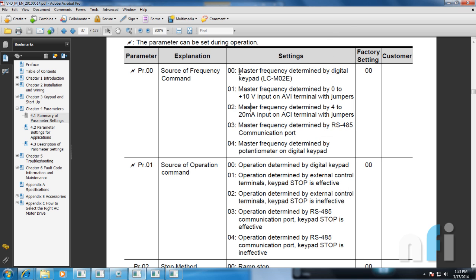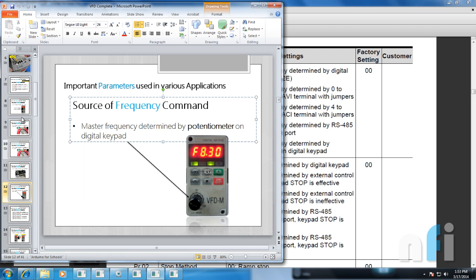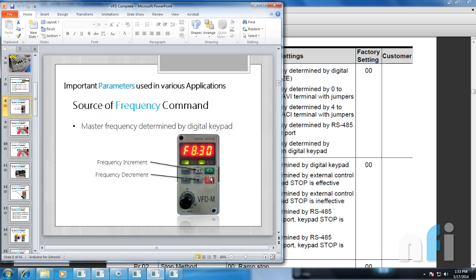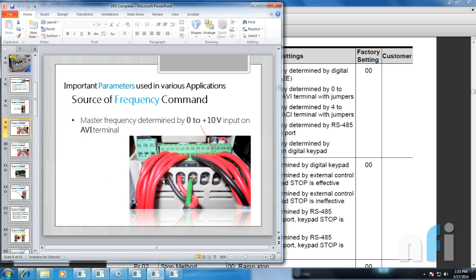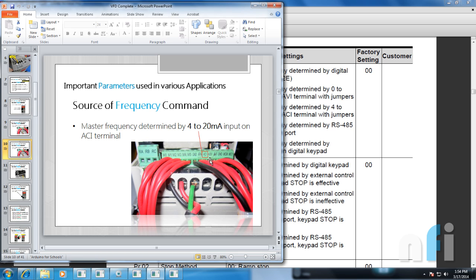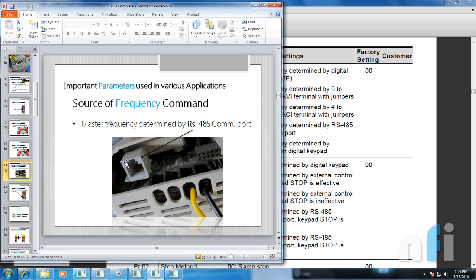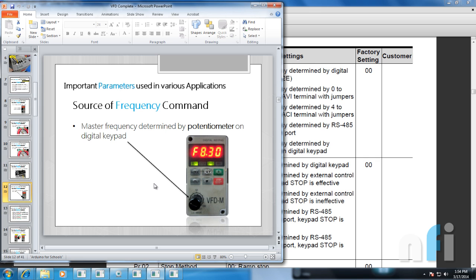So that's how you can change the frequency — we have five modes. First: frequency determined by digital keypad, using increment and decrement to change speed. Second: AVI terminal, 0 to 10 volts. Third: ACI terminal, analog current input 4 to 20 mA — quite similar to AVI, just change the source to current. Fourth: RS485 communication/Modbus — the video is already available. And the last one: potentiometer on the keypad to vary the speed. That was all about source of frequency commands in the drive.